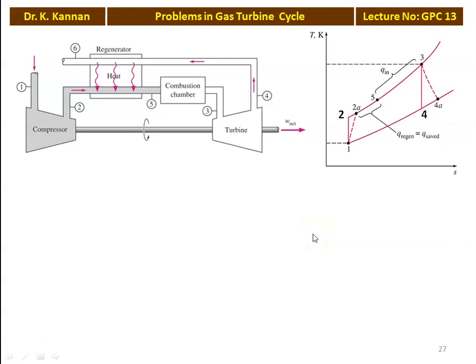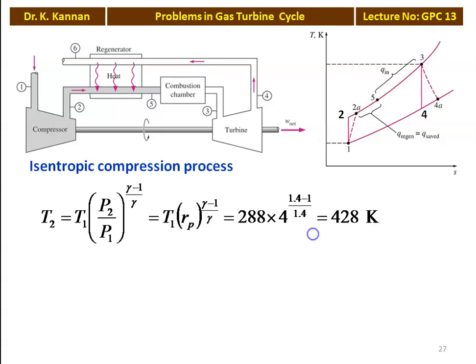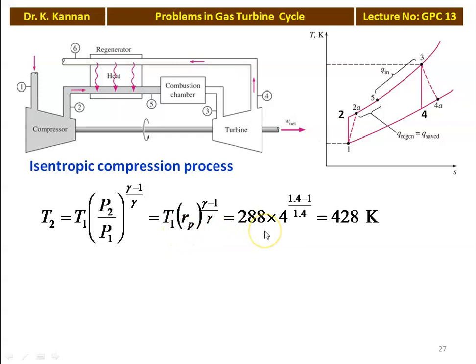This is the temperature-entropy diagram for the gas turbine cycle with regeneration, with compressor and turbine efficiency. We have to calculate the cycle efficiency of the regenerative cycle. For the isentropic compression process, we calculate the temperature T2 at the end of isentropic compression: T2 equal to T1 into (P2/P1) to the power (gamma minus 1)/gamma, which is T1 into Rp to the power (gamma minus 1)/gamma. Substituting numerical values, T1 equal to 288 and pressure ratio equal to 4: 288 into 4 to the power (1.4 minus 1)/1.4 equal to 428 Kelvin.